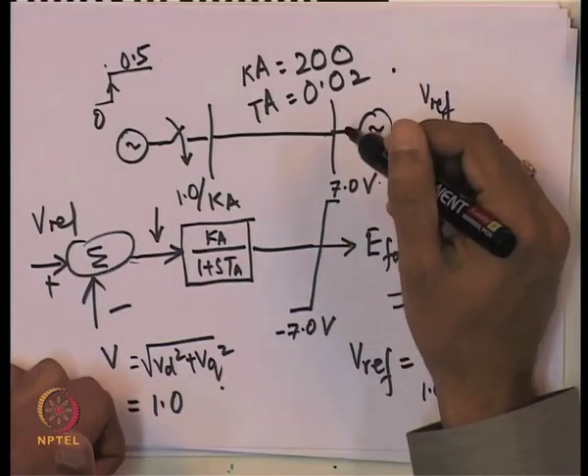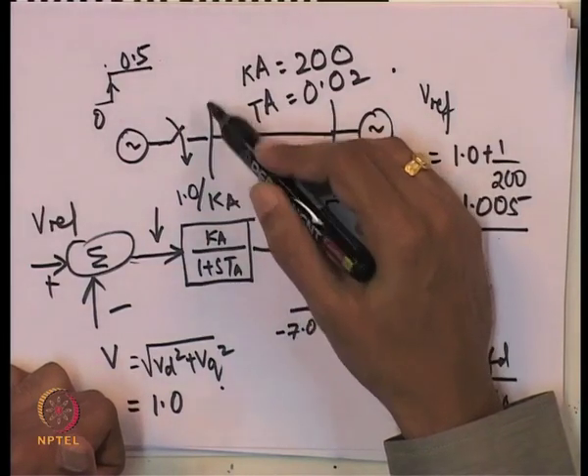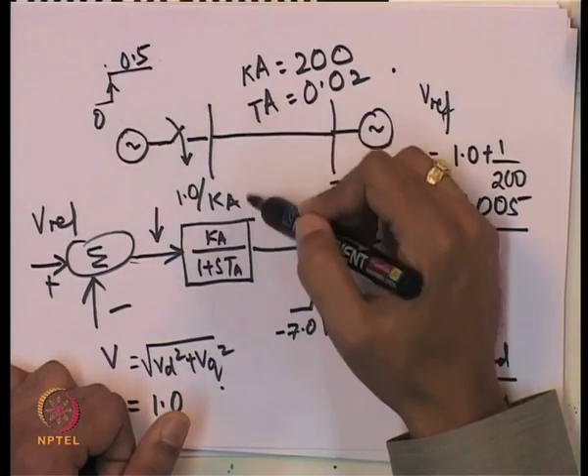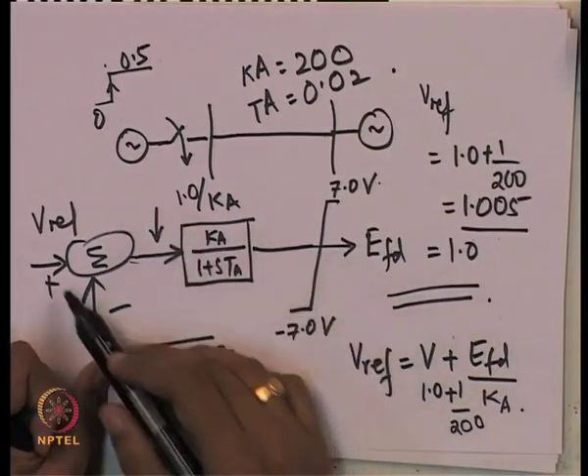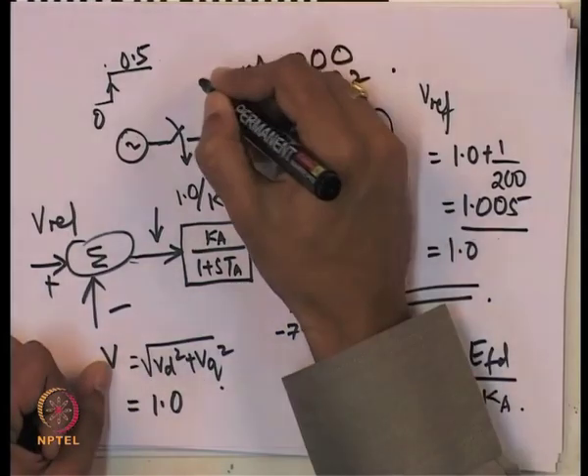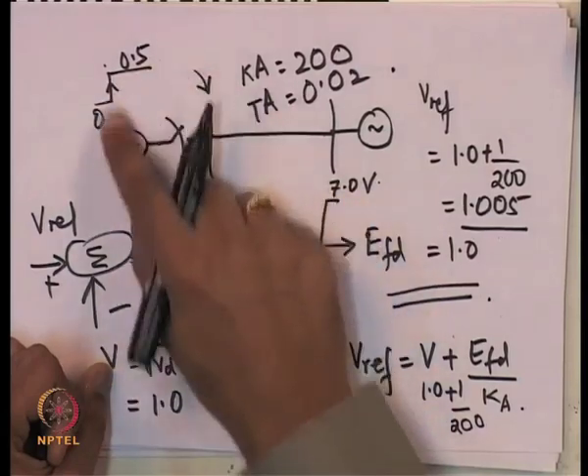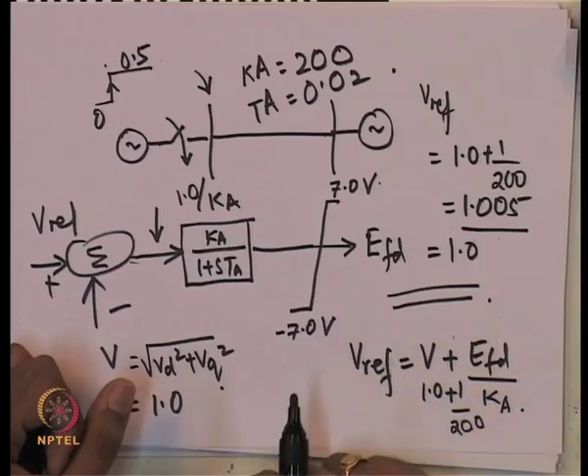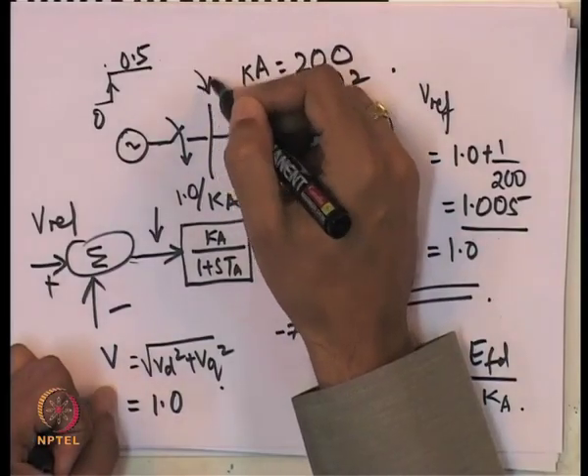As soon as some current starts flowing — that is, some power starts flowing — the terminal voltage tends to drop. Without an automatic voltage regulator, this voltage would drop and EFD would remain the same. But with a voltage regulator, as soon as V drops, Vref stays the same, so EFD is increased. This voltage is regulated and EFD is not constant. The AVR saves us the trouble of manually changing EFD every time we change the mechanical power.